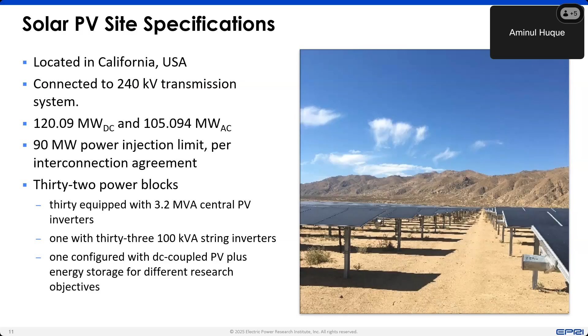And one block has a smaller string inverter, a 100 kVA string inverter, which is similar to what I have shown before, the string inverter that we tested in our lab. And the other one was a different research component, a DC coupled PV plus energy storage. But we activated this reactive power support testing for the whole plant, the entire plant.